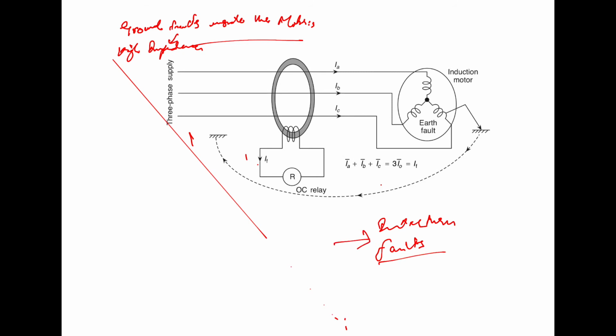Now the interturn faults on the same phase are difficult to detect because they don't cause any appreciable change in the current drawn by the motor. Such faults cause a hot spot to develop, leading to the deterioration of the insulation.